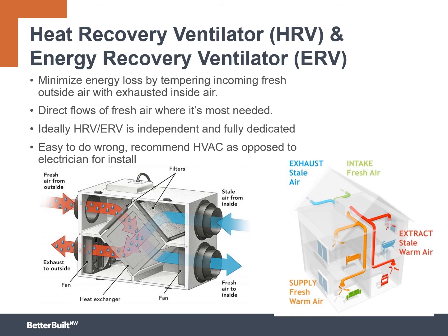First off, on cost, there are actually a number of these that we've seen for sale both online and through local distributors that meet anywhere from the minimum to the maximum efficiency range for under $1,200. So when someone says this is a $3,000 piece of equipment, perhaps when you combine all the ductwork, the controls, the piece of equipment, and the installation, it's approaching that. But if you work with your distributor, you showcase the needs that you have, you learn to do the math, and look on places like the Home Ventilating Institute website to determine what size of equipment you need, if you are willing to do a little bit of that work or have your HVAC trade do it for you, you can find a relatively cost-effective way to use heat recovery or energy recovery ventilators.